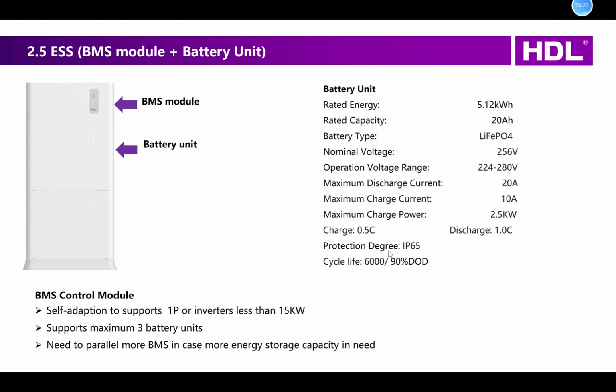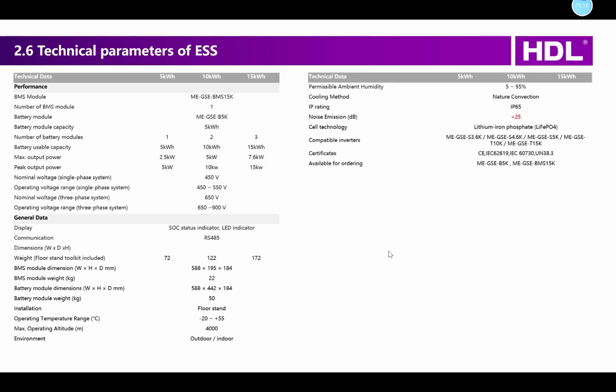For the BMS module, it can self-adapt to support one-phase or three-phase inverters of less than 15 kilowatt. One BMS module can support a maximum of 3 battery units. If you want to install more than 3 battery units to work with the inverter, you need to parallel more BMS, and the maximum right now is 3 BMS modules. So the largest BESS capacity right now is 45 kilowatt hour. Here are more details.